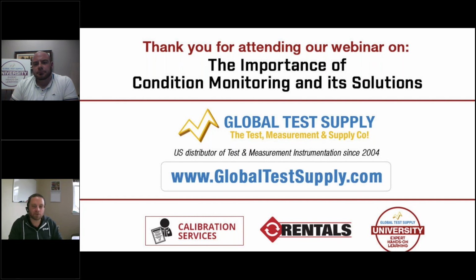We came out with a newish camera about a year ago called the GF77, a gas finding camera. This is a product you can find through Global Test Supply. The GF77 is a really cool tool because it can detect a multitude of gases and also do thermal imaging. If you want a solution that does both thermal and finds SF6, I'd go with the GF77. It has different interchangeable lenses, low range and high range, and depending on the lens, you can find SF6, methane, and different refrigerants. All the lenses also do thermal. It's like a Swiss Army knife — it can find about 10 different gases and do thermal imaging. It's a great tool to get your hands on or request a demo for.